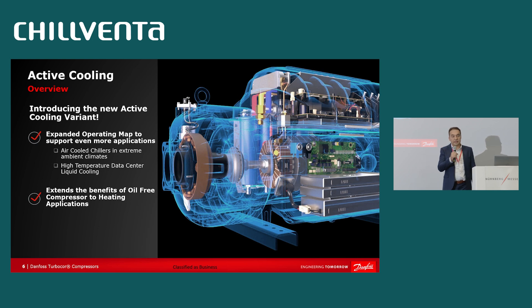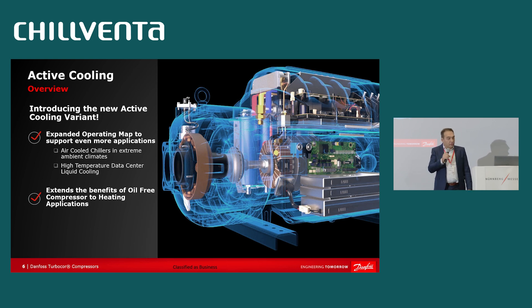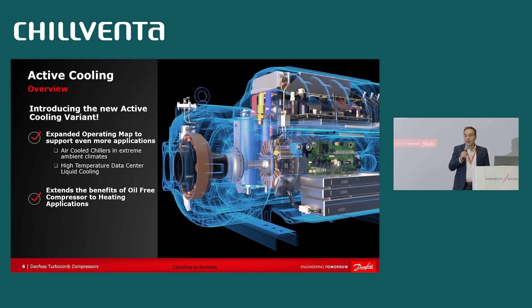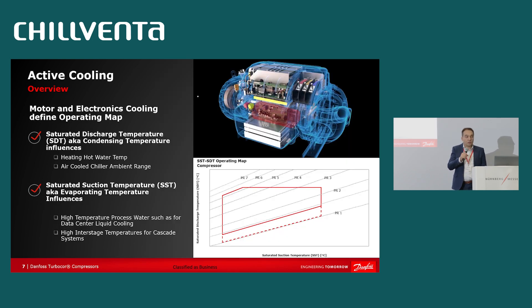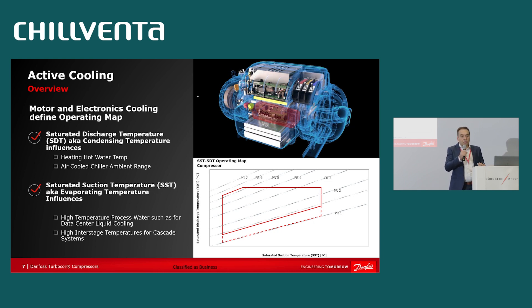Moving on to the active cooling compressor — what is it? This new version of the compressor extends the operating map to allow the oil-free compressor to reach applications which were not really accessible before. These are applications like air-cooled chillers in extreme ambience, high-temperature data centers specifically targeting the needs for liquid cooling, and most importantly for us, heating applications.